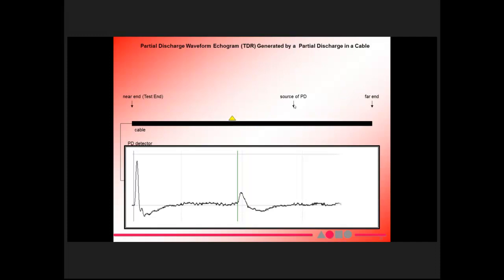You can see PD, if you have a long cable, has to travel quite a substantial way down the cable, so you do get attenuation. You can see this one here is attenuated quite a bit, because if you remember, the PD pulse that went there is a third of the way, and then it's full into the cable, so it travels 1 1/3 of the distance, where this one travels 2/3 of the distance. That's obviously bigger and sharper, where this one is lower and fatter.